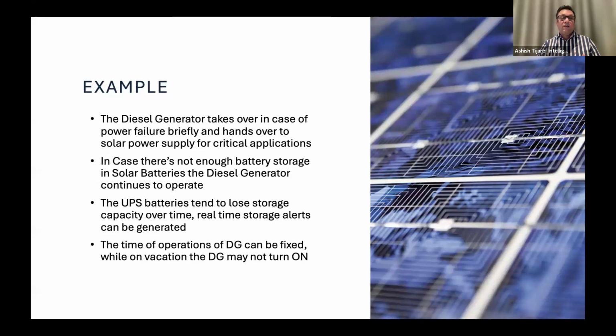We also have to see that the battery storage in solar batteries and diesel generators operate really well, so we can use as much solar power as possible and reduce diesel consumption. UPS batteries, over a period of time, tend to lose storage capacity, so we have to monitor that too. If the battery health goes down, let's say below 75% or 50%, then it's time to change the UPS battery.